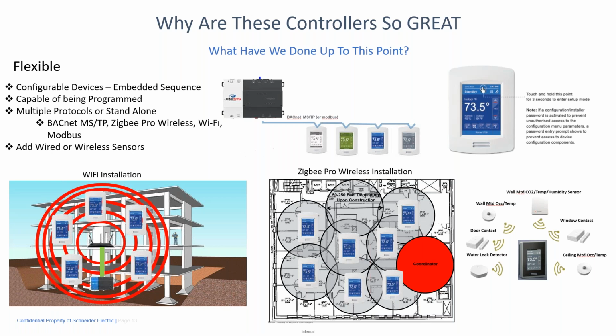They all communicate because they're all on the same PAN and channel, so the communication is assured. Up in the top center portion of it is your standard BACnet MSTP or Modbus daisy chain type of environment, right? Again, these all have time clocks and schedules on them, so you can use them in a standalone environment. And then again, you can add the wireless sensors, either wired or wireless, right? So I can add wired sensors to these devices, or again, I can use the wireless Zigbee communications to communicate with up to 20 of those controllers.